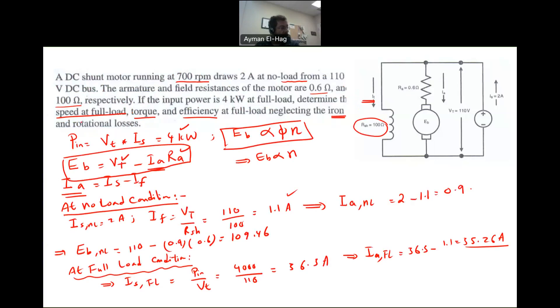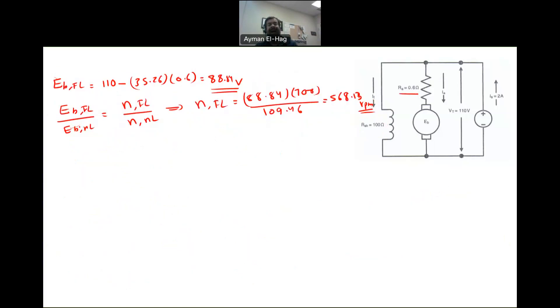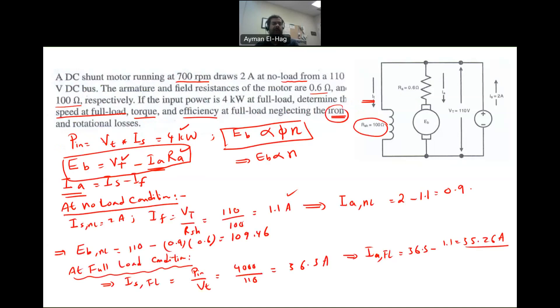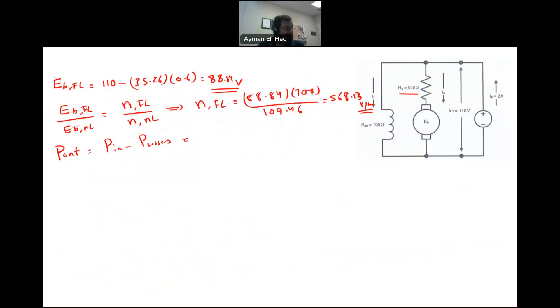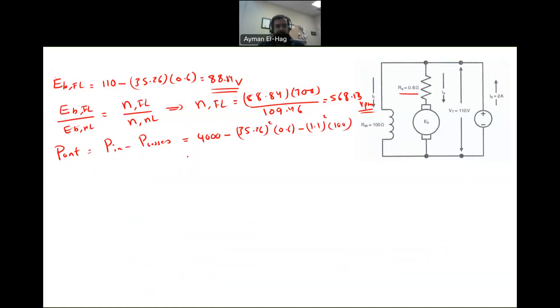That is the first requirement: speed at full load is 568.13 RPM. Now we find the output torque, which requires the output power. P_out equals P_in minus losses. Neglecting iron and rotational losses, we have only I²R losses: 4000 minus 35.26² times 0.6 minus 1.1² times 100, giving P_out equal to 3133.03 watts.